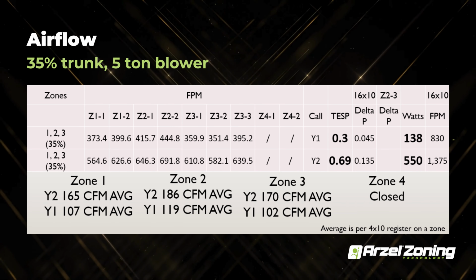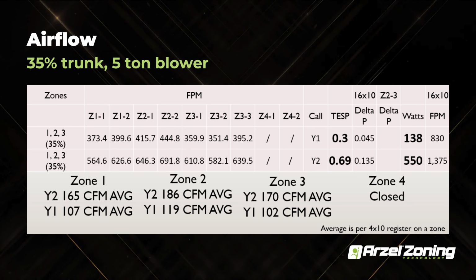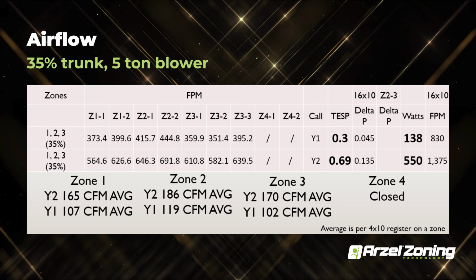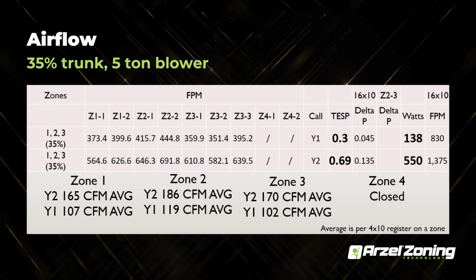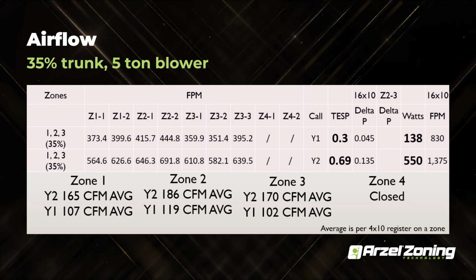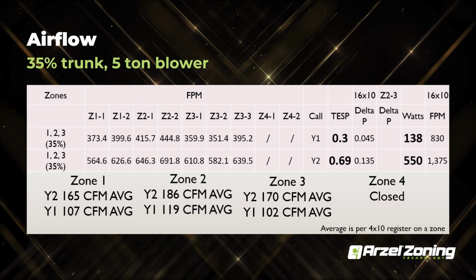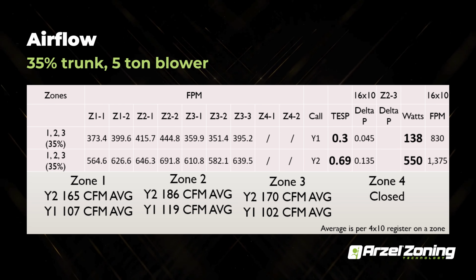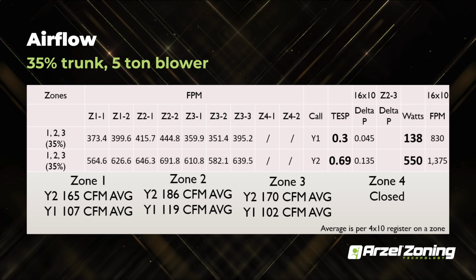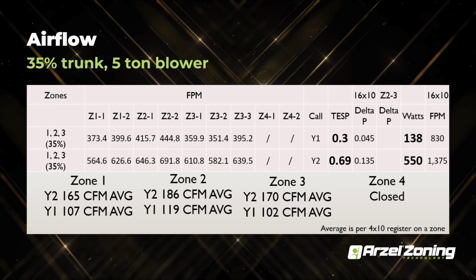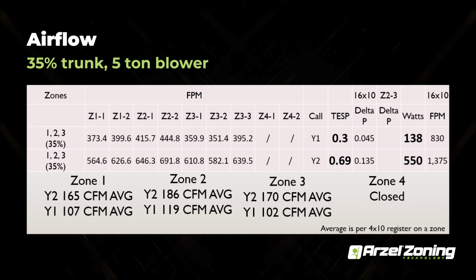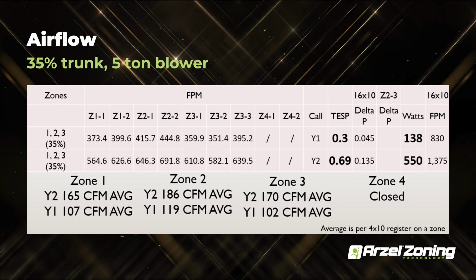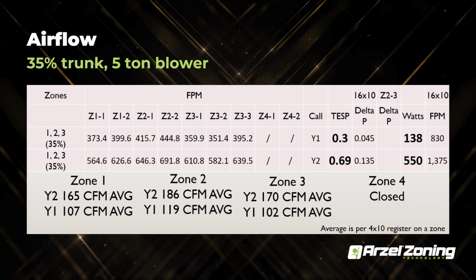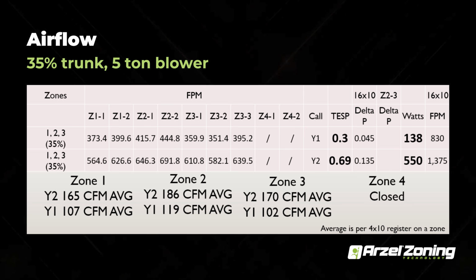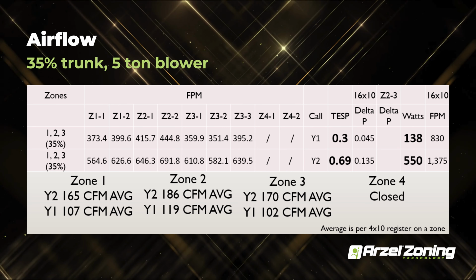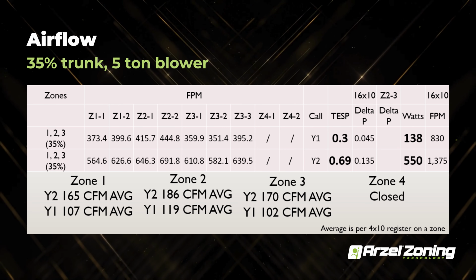When you're locking out another zone, essentially we're dropping this to 35% of our equipment potential, so our actual smallest zone is no smaller than 35% of the duct here. This is really what you're looking for if you're doing a PSC motor. If you're zoning that piece of equipment, you never want your smallest zone smaller than 35% of your overall trunk. Just a rule of thumb, and that's with a minimal bypass. Just keep that in mind.